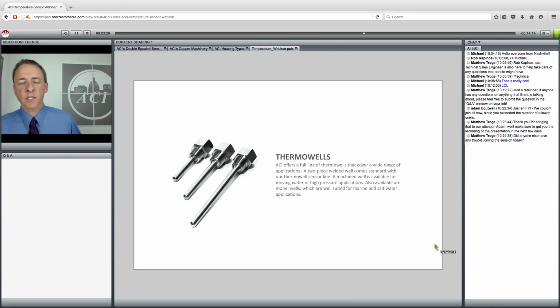Our Thermowells we talked about briefly a minute ago when I went through the lengths of our Thermowells. Our standard well lengths are 2.5-inch, 4-inch, and 6-inch, and that's from the base of the thread to the tip of the probe. By custom order, we also have longer Thermowells available, up to 24 inches. As of today, our standard Thermowell is a 2-part fabricated well, where the probe part of the well is welded to the thread part of the well.